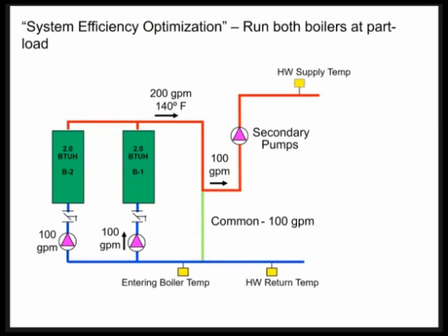My supply water temp is 140. My return flow rate and temperature is 100 GPM and 100 degrees. Again, I've got 2 million BTUs worth of load. What happens down here at the entering boiler temp? Because I have 100 GPM of 140 degree water coming down my common pipe, mixing with 100 GPM of 100 degree water, my entering boiler temperature has gone up to 120 degrees.